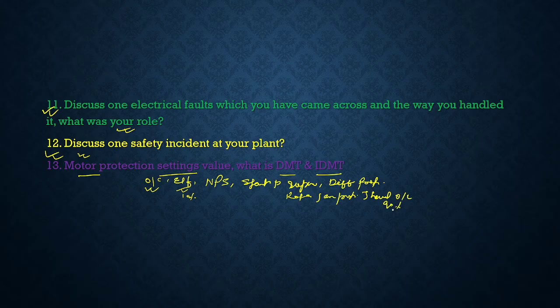Thermal overload we use 90% setting. So these are the basic settings that you have to remember for the interview. We also use earth fault and overcurrent in two stages, where we have definite time and IDMT time. So you can tell those settings.